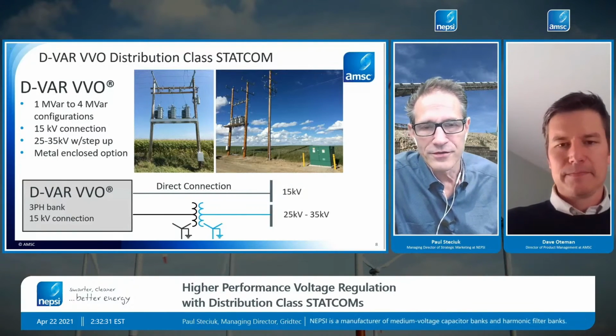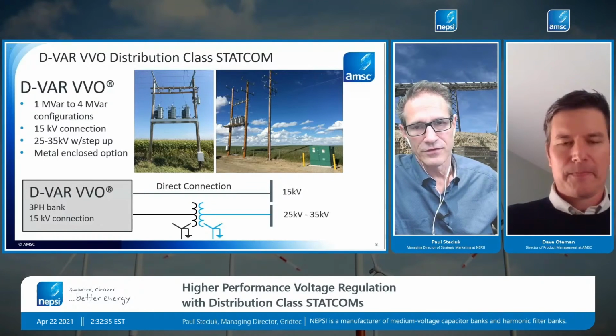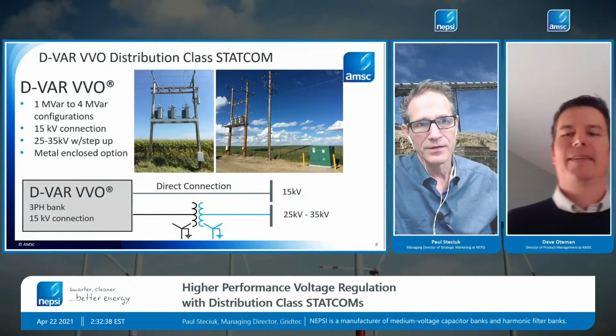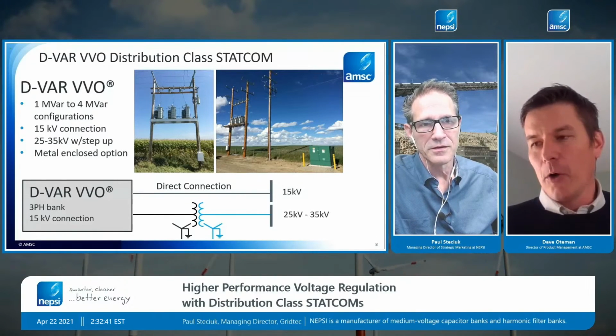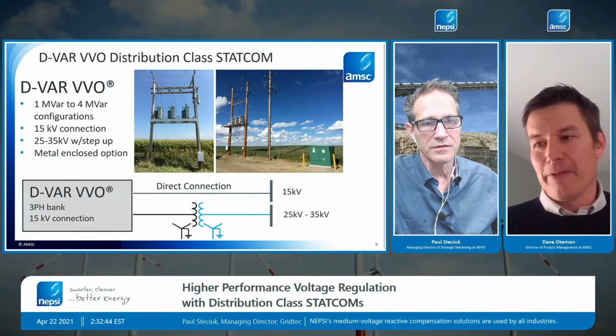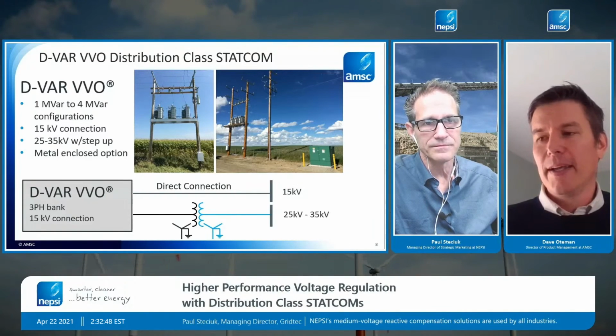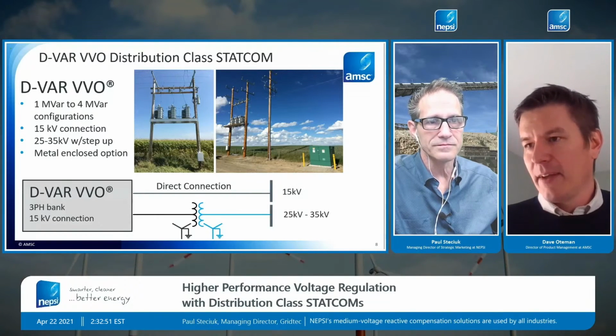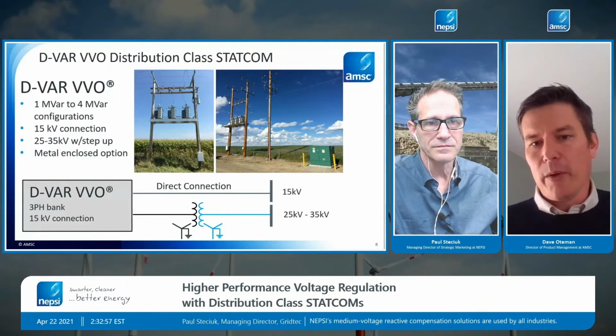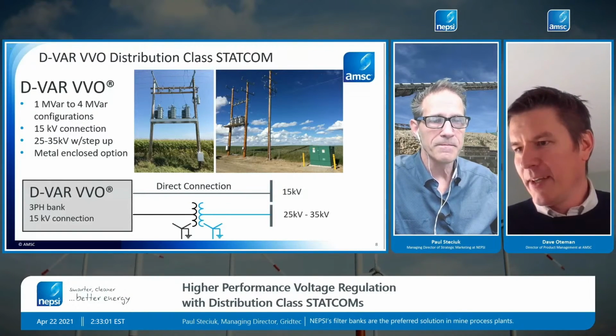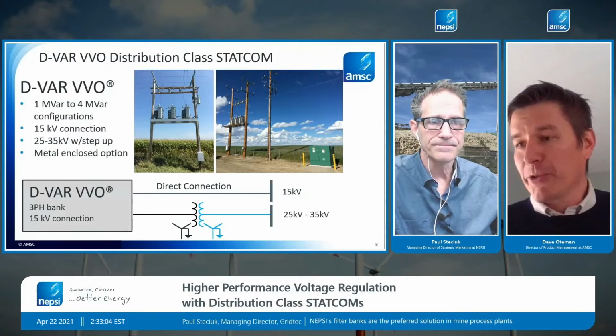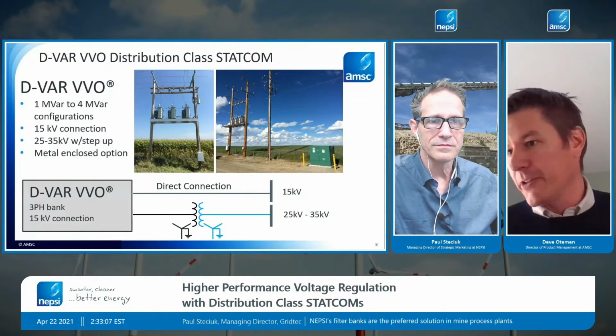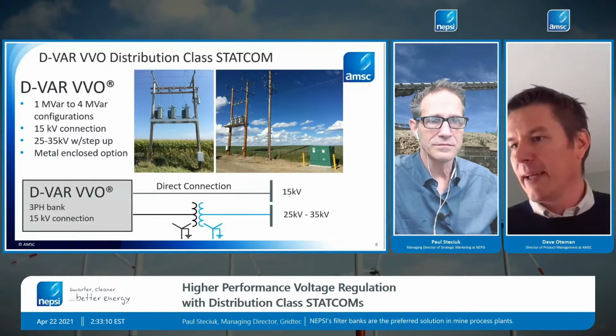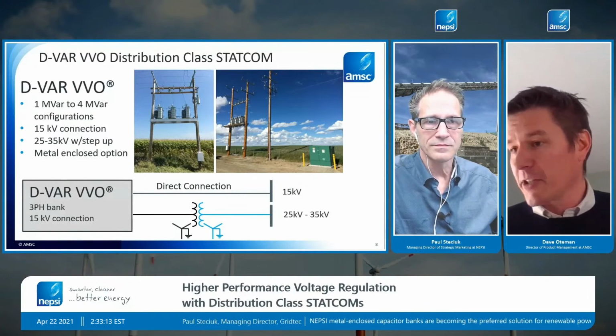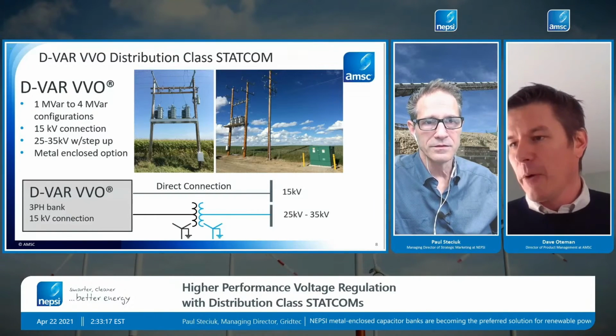Maybe comment on why you went with 15 kV versus 25 kV. That's a great question. Around 80% of distribution infrastructure in North America is still 15 kV class, so that hits the sweet spot of the market need, and we were able to do that most cost effectively. The step-up transformer is one most utilities already use elsewhere in their system, so it's familiar, easy to buy, not expensive, and very reliable. That was the right choice.